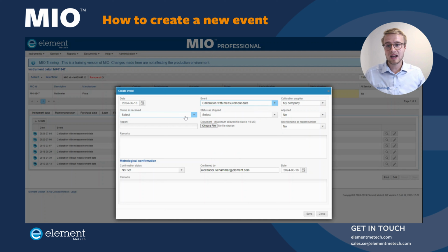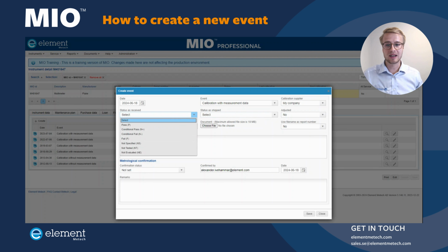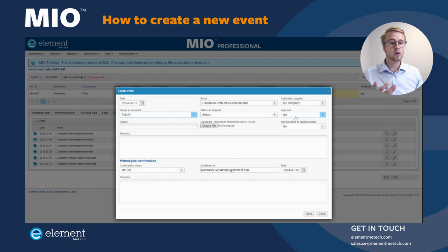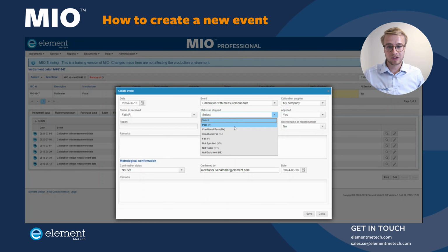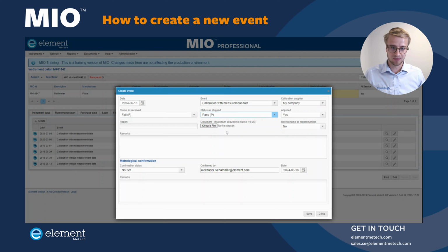Then we're going to add the status as received. So let's say that we calibrated this multimeter and it did not pass the calibration. It was a fail according to the specification. Then I will add that status as received. And then we perform an adjustment of the multimeter and recalibrated the measurement instrument, and it passed for a second calibration as shipped.